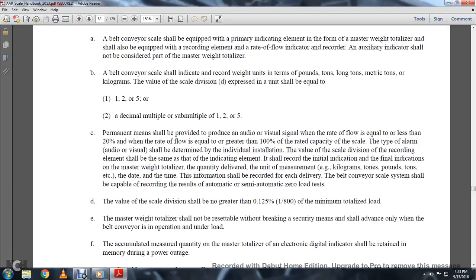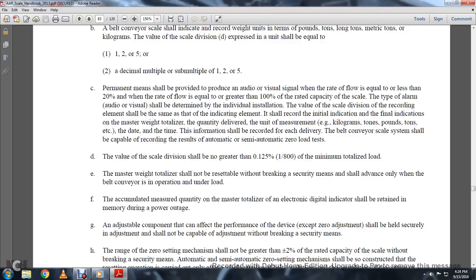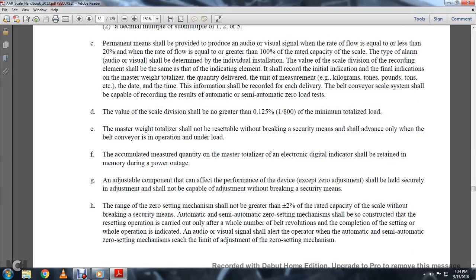The recording element shall record: initial indication, final indication of the master weight totalizer quantity, any quantity delivered in units of kilograms, tons, or pounds, the date and time of delivery. The belt conveyor scale system shall be capable of recording results automatically or semi-automatically, including zero load testing. The value of the scale division shall be no greater than 0.125% or 1/800 of the minimum totalized load. The master weight totalizer shall not be reasonably resettable without breaking the security means. Adjustments shall not be capable of adjustment without breaking security measurements.